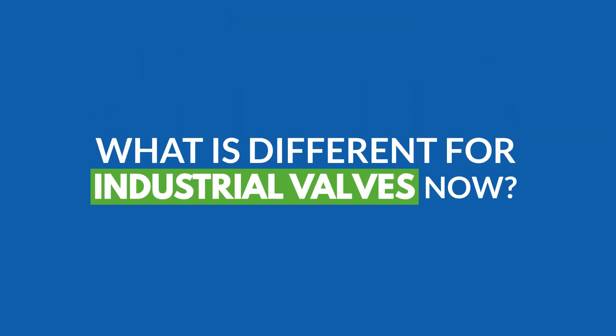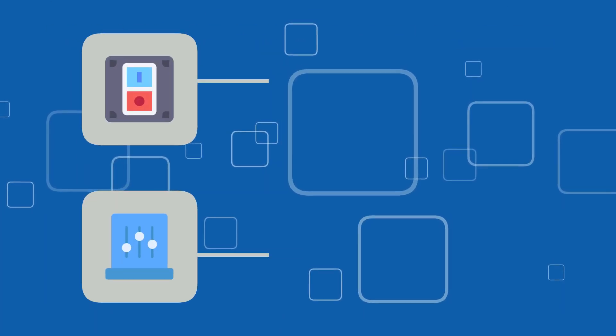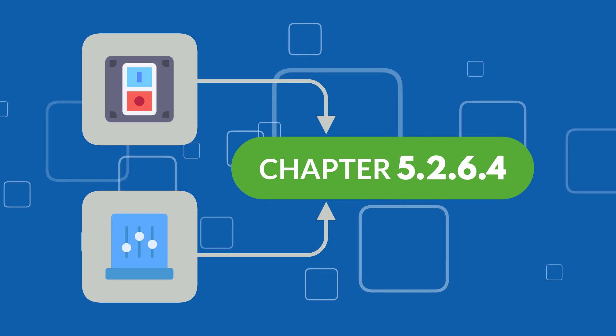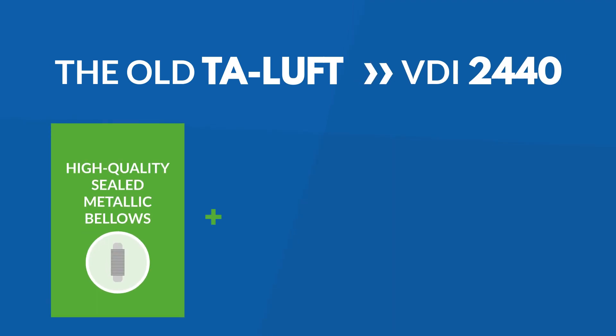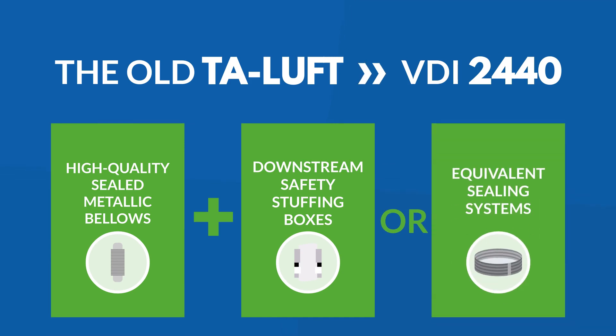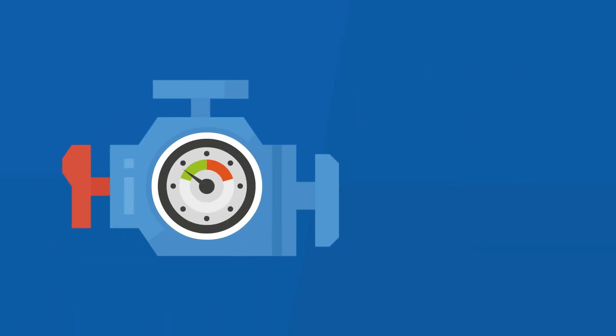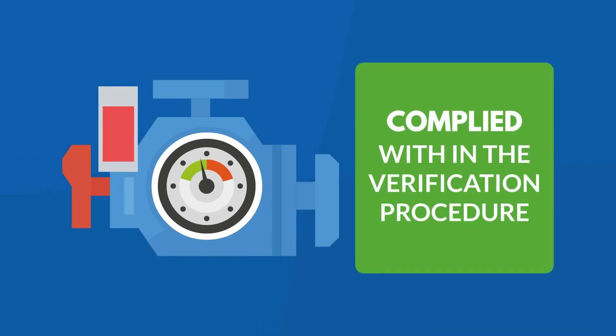So what is different for industrial valves now? The core changes are for shutoff and control elements as highlighted in Chapter 5.2.6.4. With the old TA Luft in accordance with VDI 2440, only high-quality sealed metallic bellows with downstream safety stuffing boxes or equivalent sealing systems could be used. In addition, sealing systems were regarded as equivalent if the temperature-specific leakage rates were complied with in the verification procedure.